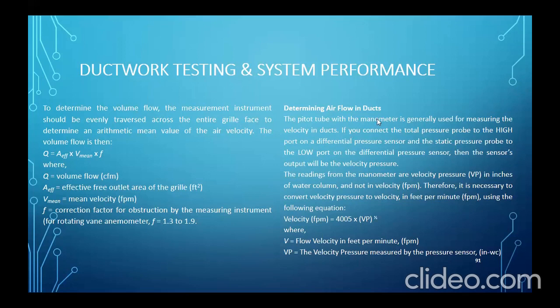Now, determine the airflow in a duct. So yun nga, the pitot tube with manometer is generally used for measuring the velocity in ducts. If you connect the total pressure probe to the high port on the differential pressure sensor and the static pressure probe to the low port, then the sensor's output will be velocity pressure. So the readings from the manometer are velocity pressure in inches of water column and not velocity in feet per minute. Therefore, it is necessary to convert velocity pressure to velocity in feet per minute using the following equation.